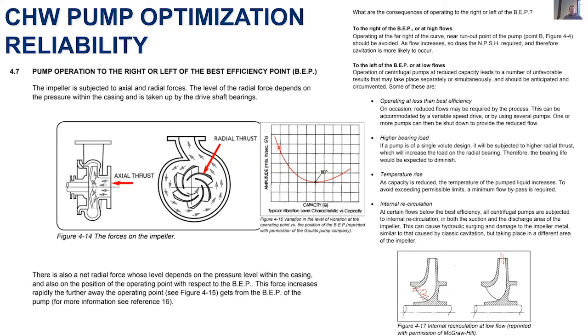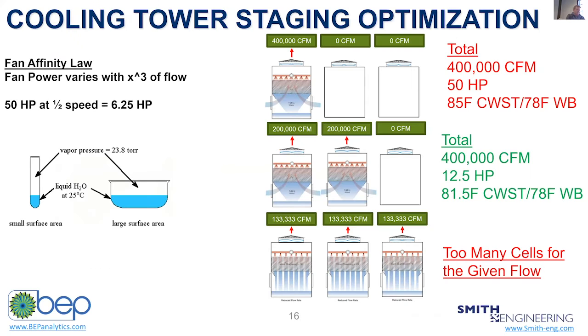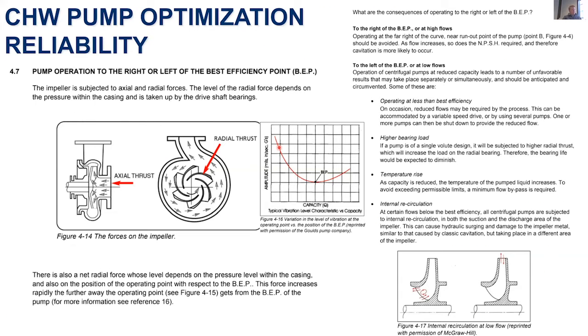Also, the bearing life is a function of speed, and the pump is running at a lower speed. So the pump is really happy right now. It's going to last a lot longer, and we're saving energy. So that's a pump example. I know I went through it pretty quickly, but I think you get the concept. There's a lot of savings that can be done there, and it's a fun one to play with.